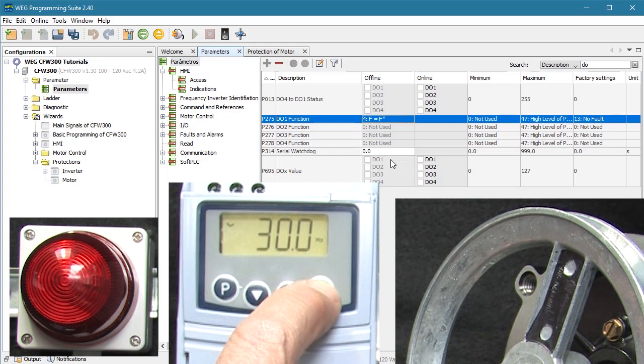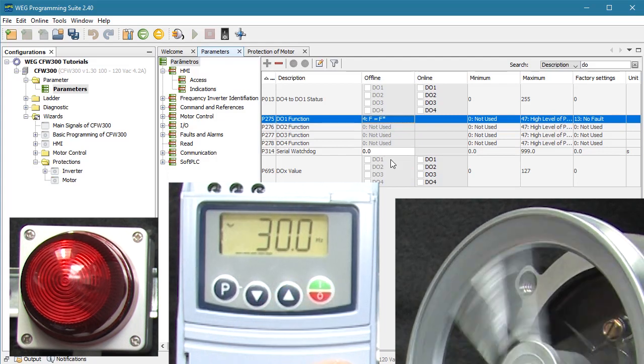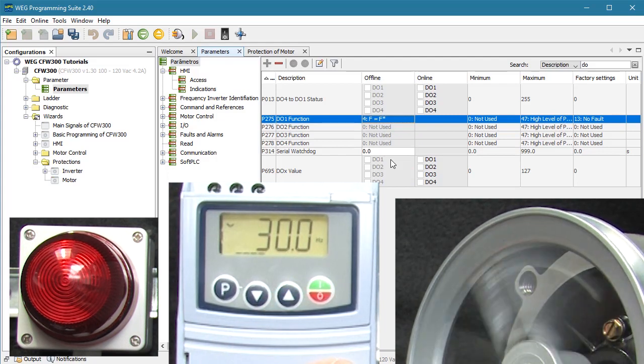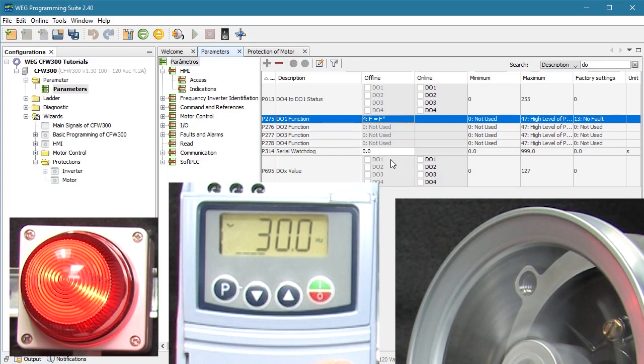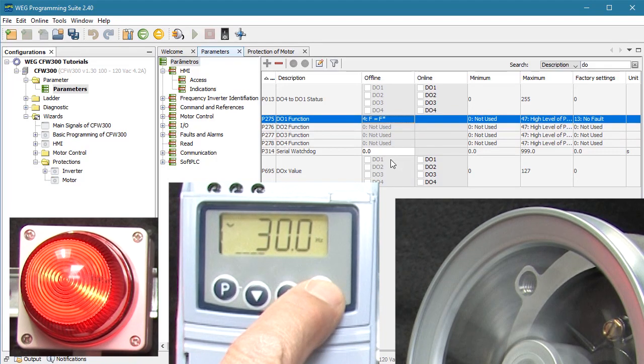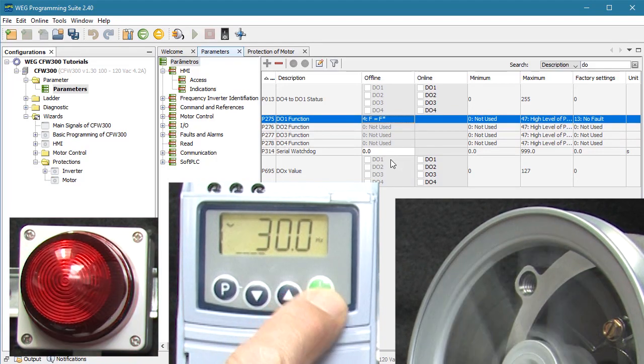If I hit run — counting about 2.5 seconds — bingo. The indicator turned on when the output frequency reached the reference frequency. Perfect.